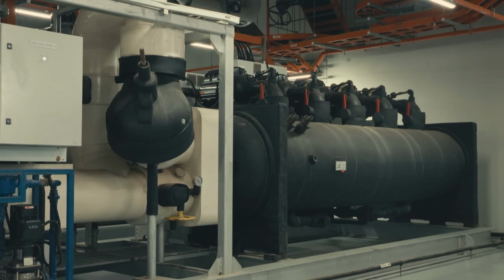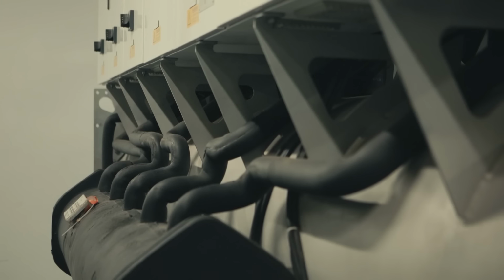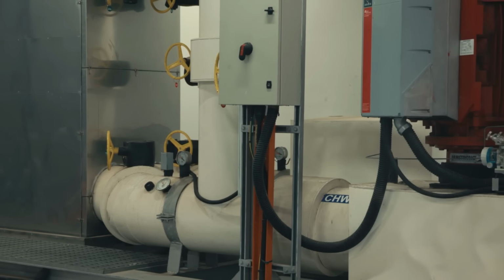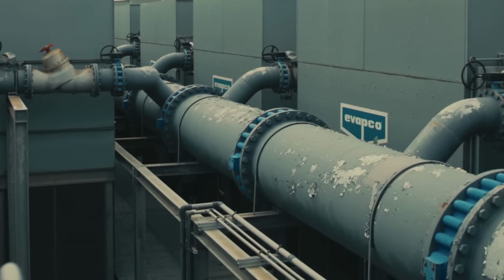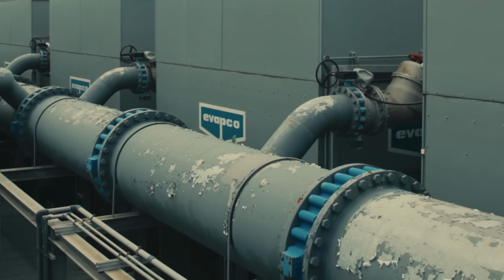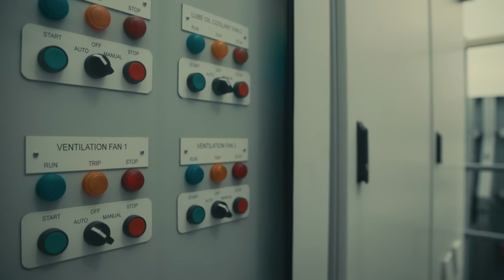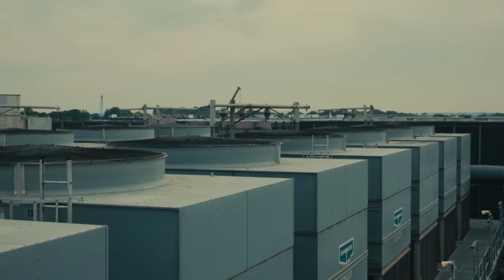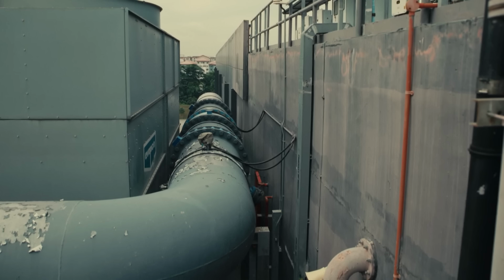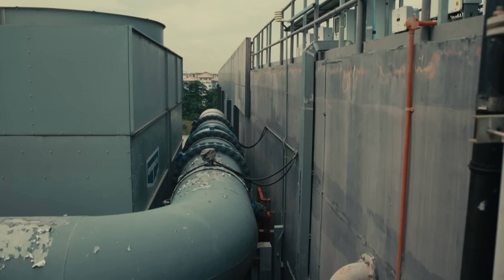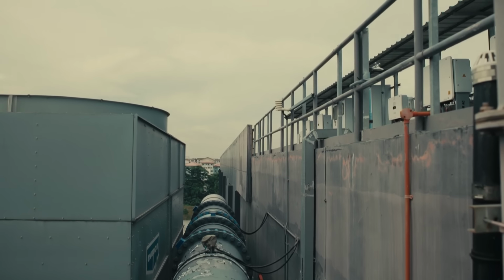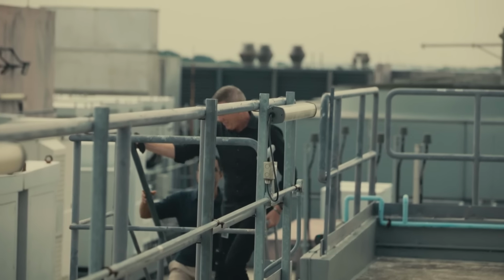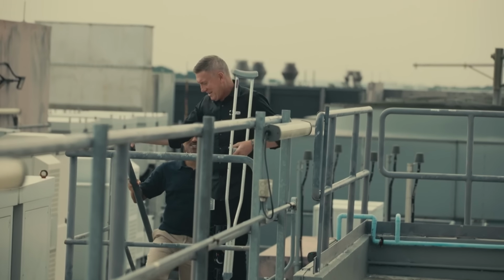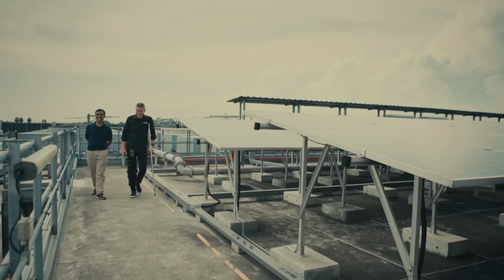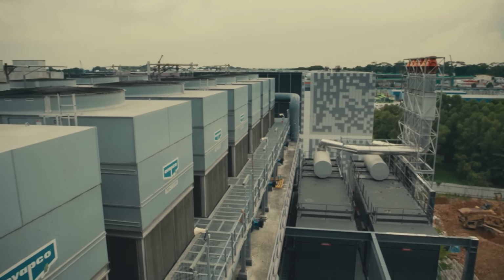One of the things is using our chillers more efficiently. We're trialing an AI tool at the moment that's looking at water flow, even down to the amount of water flowing through a valve at any particular time. Our AI system looks for patterns and helps suggest where we might reduce energy - it might be a fan running at 80% that we can turn down to 60%, or a valve where opening it a bit more gets more water through. As the temperature changes outside during the day, we're trying to move the building to match the outside climate - whether humidity spikes up or it's cooler in the early morning, we try to get the building to flex towards those changes.